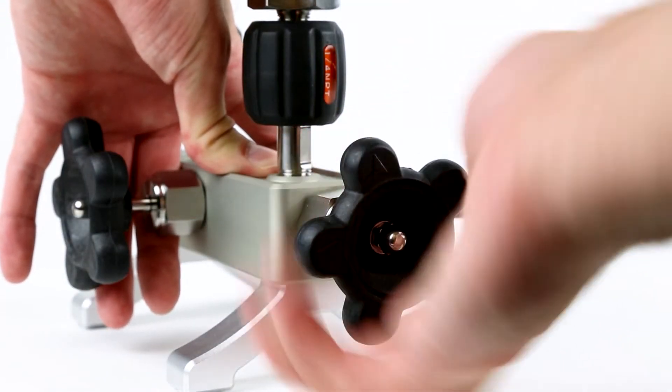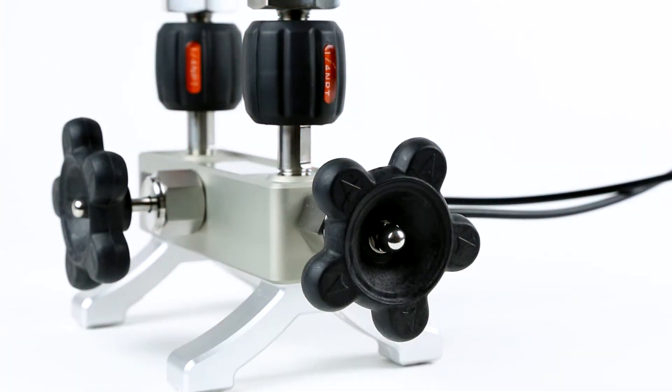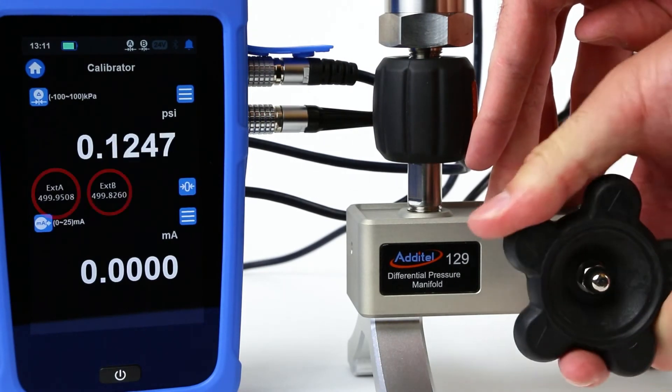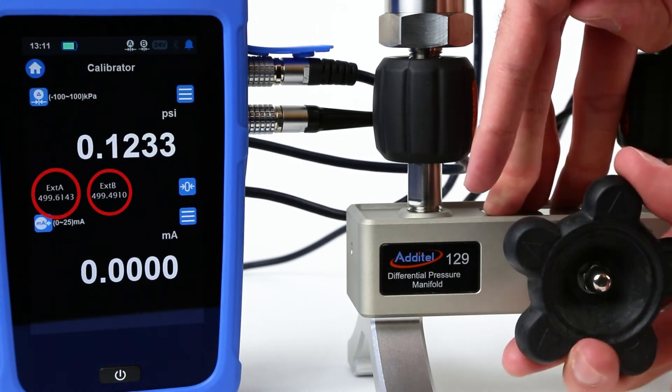To perform the high static pressure differential measurement, we start by closing off the high pressure line from the low pressure port. We next ensure that the valve in the front is open so that both pressure modules are seeing the low line pressure.